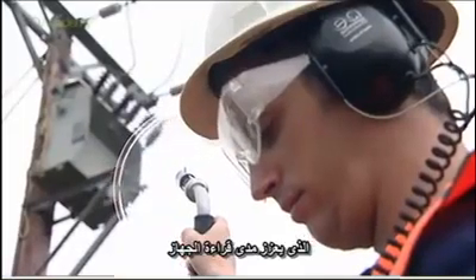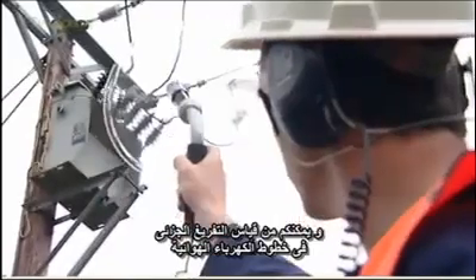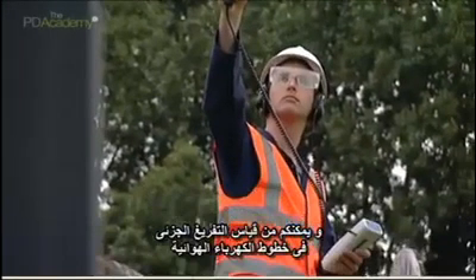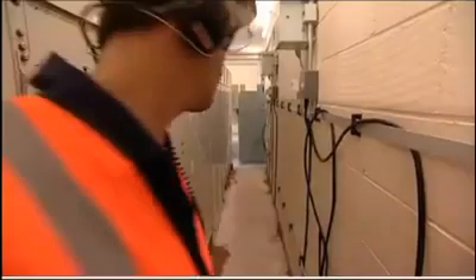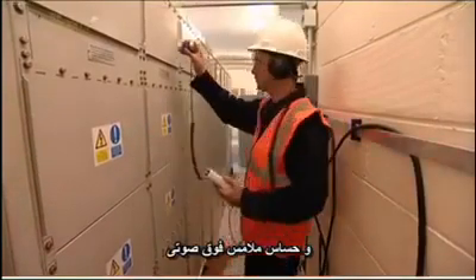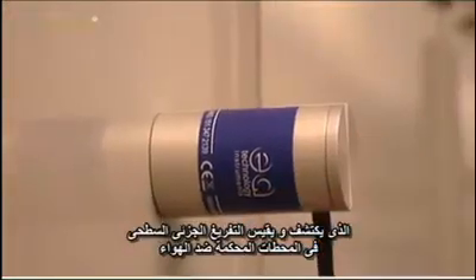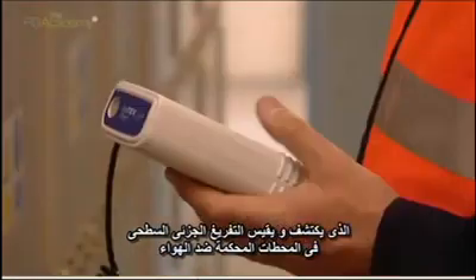And you can add a directional microphone, which increases the instrument's range and enables you to check for PD activity on overhead assets and hard-to-reach places in your plant. And an ultrasonic contact probe, which detects and measures surface discharges in sealed chambers, such as cable boxes.